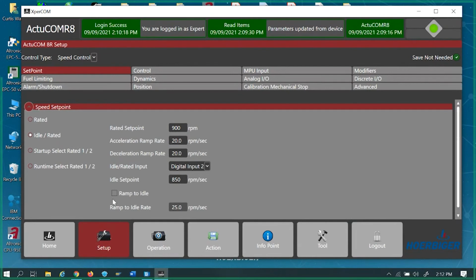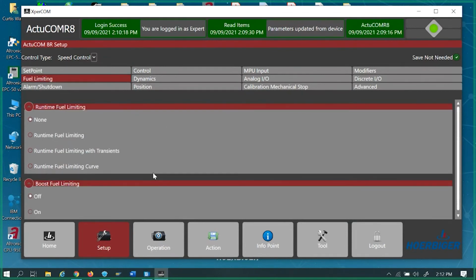We'll get to that real quick. Then we have a ramp to idle. Basically, when you're going back down to the idle RPM, even coming off rated, it'll ramp down pretty slowly instead of just hammering it down. Fuel limiting: I haven't really messed with any of the fuel limiting or transients or the boost limiting. I haven't run into that application. If any of y'all do, we'll try to address it then.